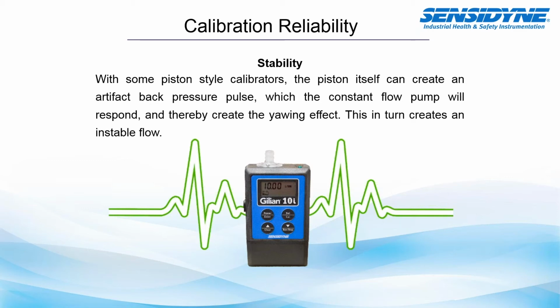If you can imagine you have a piston puck that moves within a cylinder. If that puck were to be raised up and dropped, there's a little pulse or pressure wave that gets pushed back to the pump being calibrated. If your pump is in constant flow mode, it will respond to what it perceives as a change in pressure and then speed up or slow down the motor speed. And that will create that yawing effect.